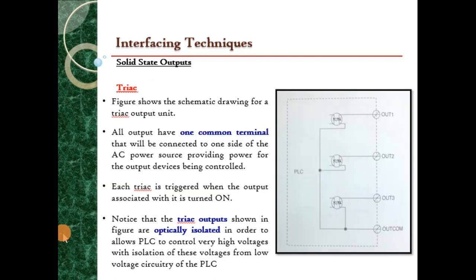Now we move to triac. Triac stands for triode for alternating current. It is a bi-directional device that has three terminals that can pass the current in both forward and reverse bias conditions. Hence, it is an AC control device. So all outputs have one common terminal that will be connected to one of the AC power source, providing power for the output devices being controlled. Each triac is triggered when the output associated with it is turned on.